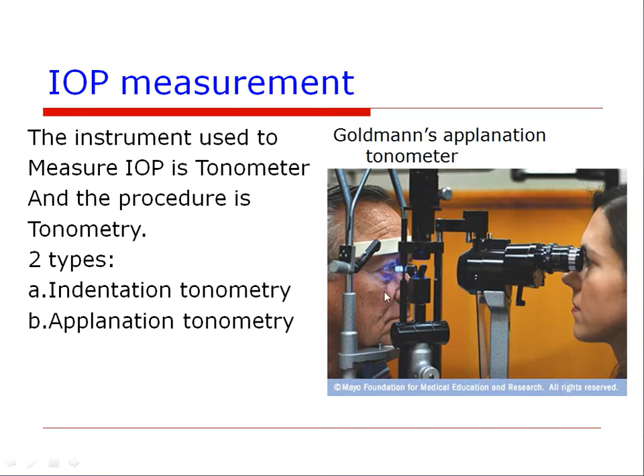The applanation tonometer will have a prism. You can see a small circle. This circle here will be around 3 mm. This 3 mm will go and touch the central cornea of the patient. That's what we were discussing. When the central cornea is very thick, the measured IOP will come as high, whereas when the central cornea is thinner, the measured IOP will come falsely low. Because the central 3 mm is the area where the applanation tonometer is touching the patient.